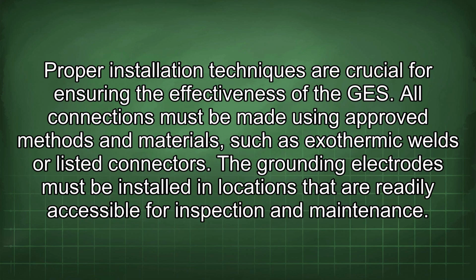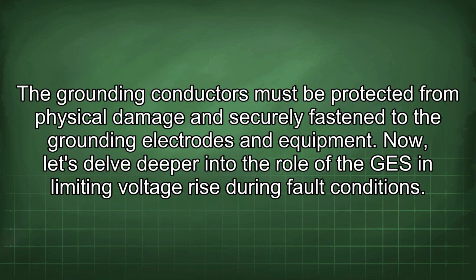Proper installation techniques are crucial for ensuring the effectiveness of the GES. All connections must be made using approved methods and materials such as exothermic welds or listed connectors. The grounding electrodes must be installed in locations that are readily accessible for inspection and maintenance. The grounding conductors must be protected from physical damage and securely fastened to the grounding electrodes and equipment.